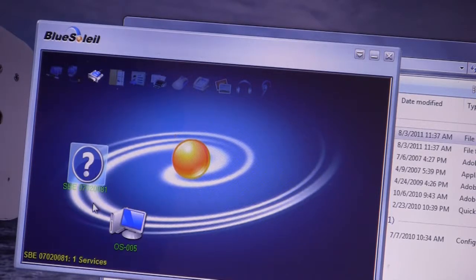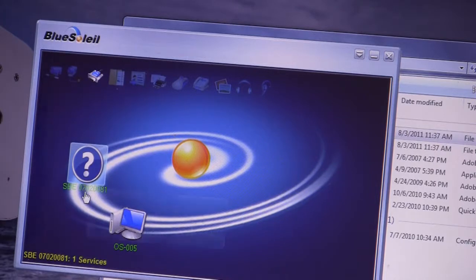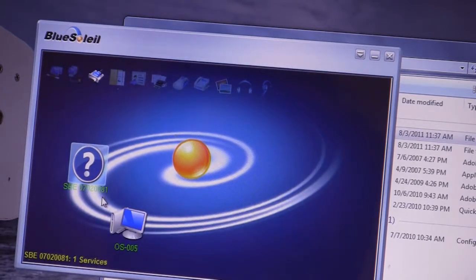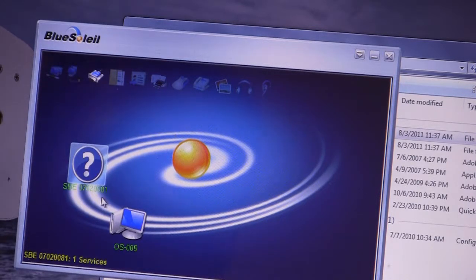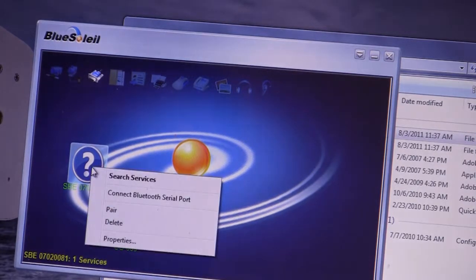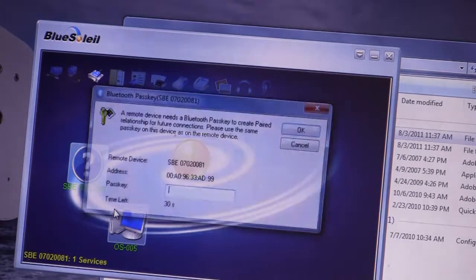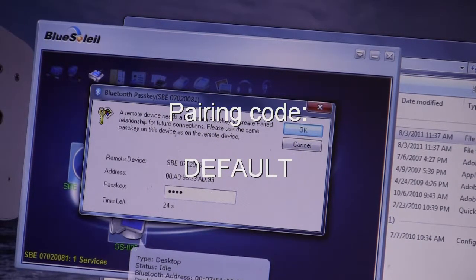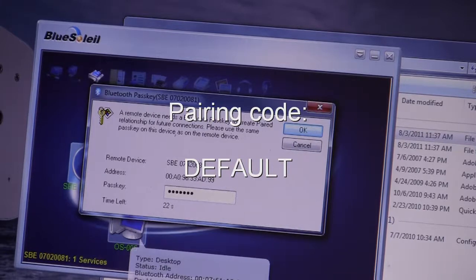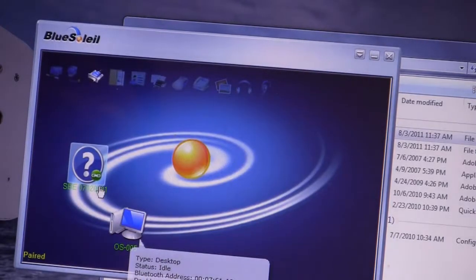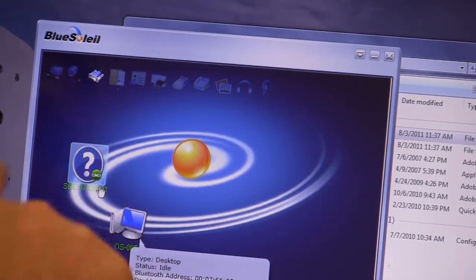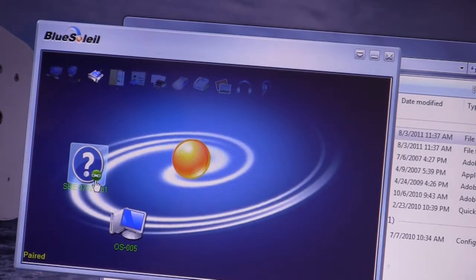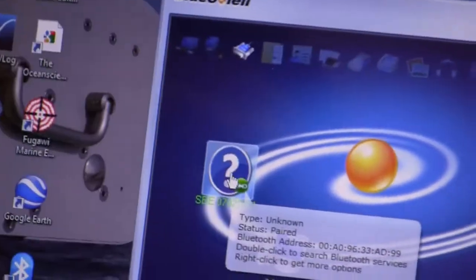Here is the Seabird probe listed as SBE 07020081. Now we're going to pair this probe with the Bluetooth adapter. I just right click and pair. The pass key you enter is default: D-E-F-A-U-L-T. Return. And when it's paired, a little chain appears here to see that the two are now locked together.